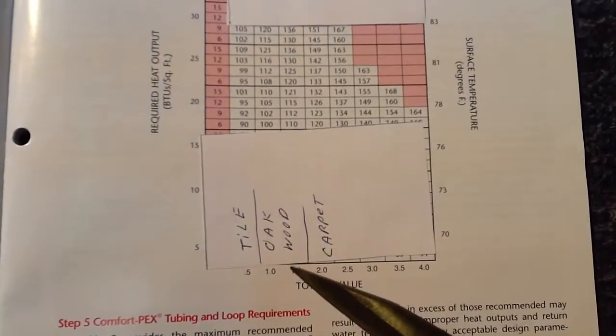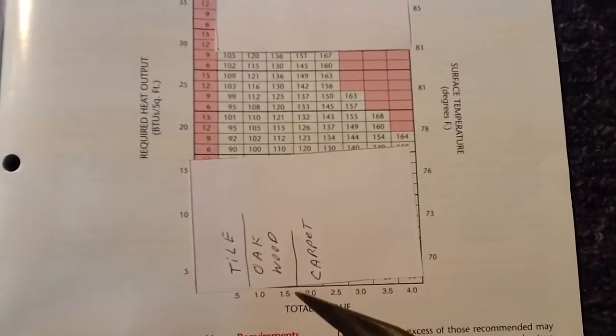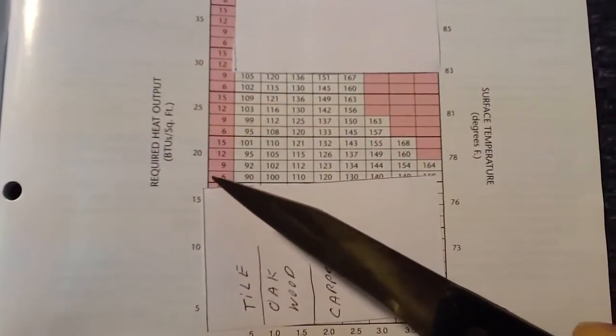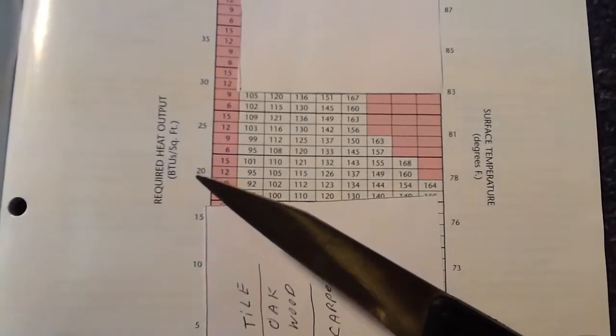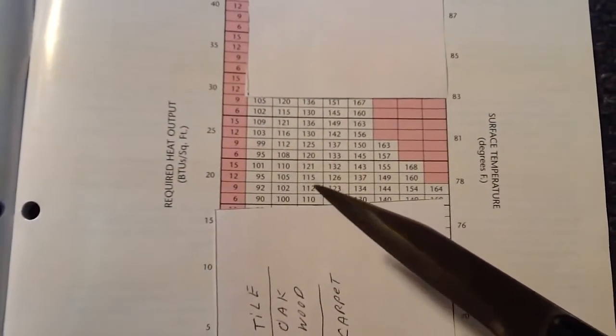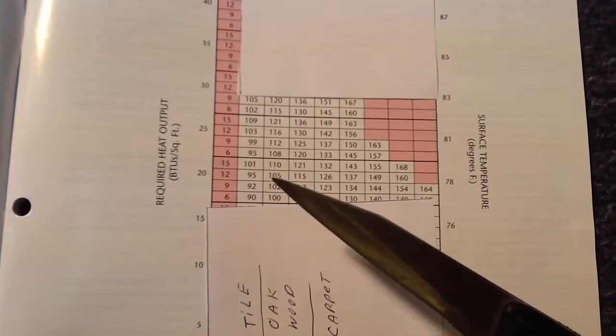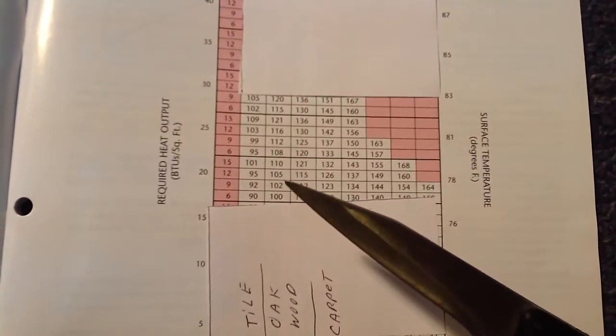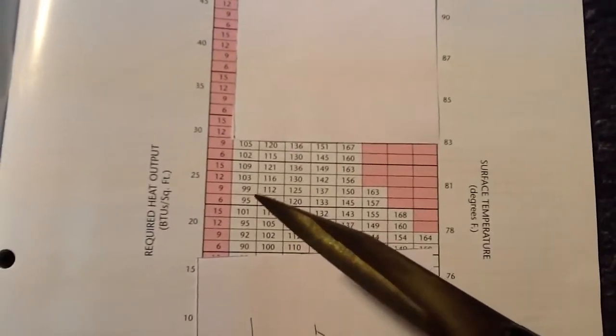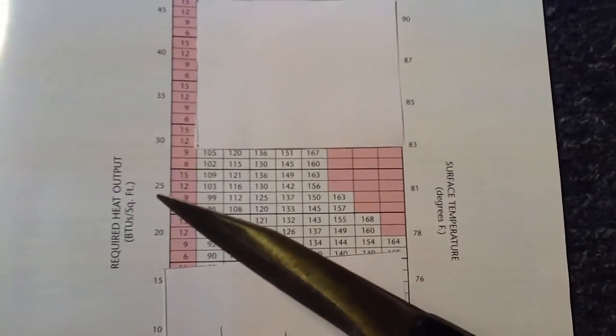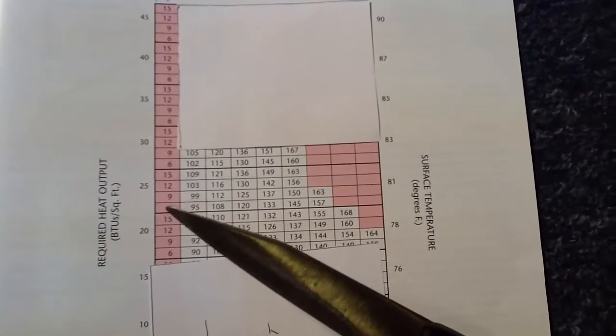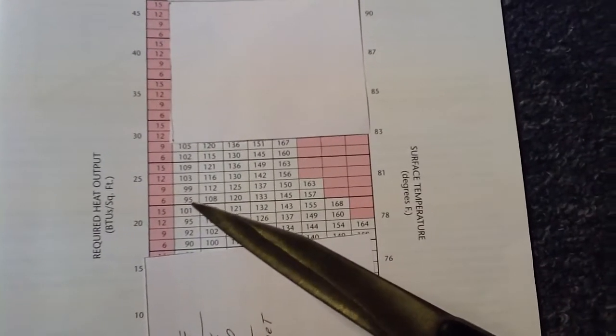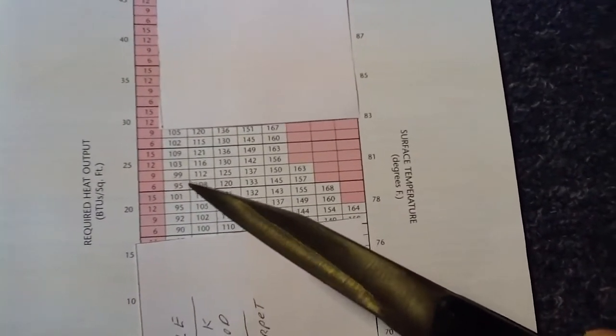Once you start getting to thick wood floors or carpet, the water temperature gets higher. To achieve 20 BTUs per square foot, you start to need 105-degree water at 12-inch spaces, and 102-degree water for 9-inch space loops. As you want to achieve higher heat, 25 BTUs per square foot at 6-inch loops, with tile, you would need 95-degree water.